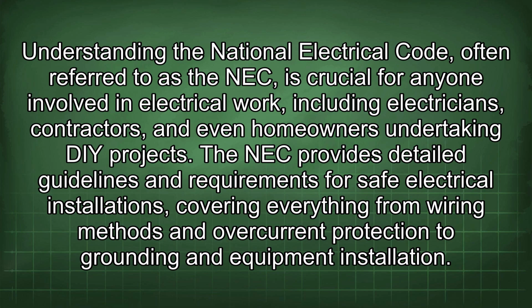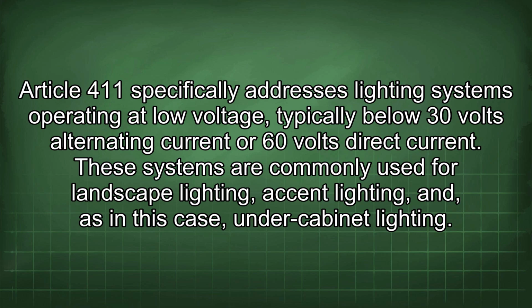The NEC provides detailed guidelines and requirements for safe electrical installations, covering everything from wiring methods and overcurrent protection to grounding and equipment installation. Article 411 specifically addresses lighting systems operating at low voltage, typically below 30 volts alternating current or 60 volts direct current. These systems are commonly used for landscape lighting, accent lighting, and, as in this case, under-cabinet lighting.